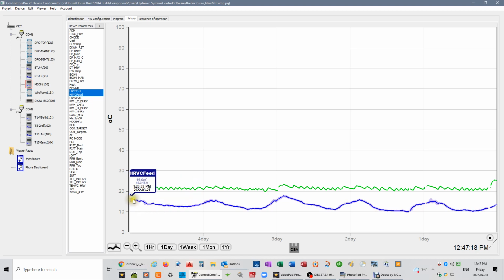And so the temperature coming in is going to be very similar to the outdoor temperature. So I select it here, and you can see it's just showing there. It's not showing for the rest of this. This is because I did not select this variable to store as a history parameter in my iNet. And so I'm only getting it based on the time that I've started to run this history graph. So that's not going to help us much, but you can see how it's dipping down at the very early morning, just before breakfast, which is the coldest time of the day, and you can see how it dips down every day. But I have been able to maintain a fairly consistent output temperature of 20 to 21 degrees, even up to 22 degrees, which is phenomenal.